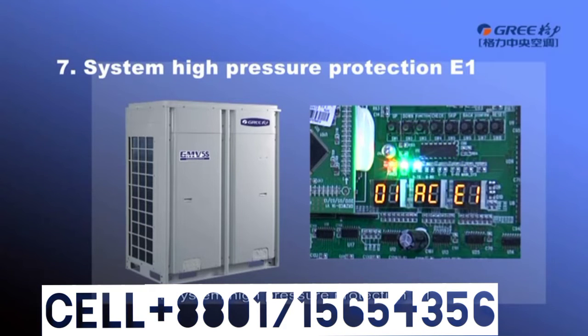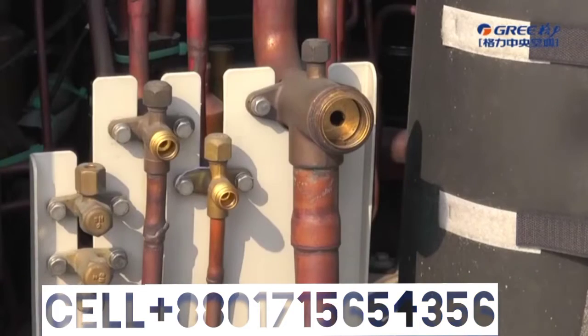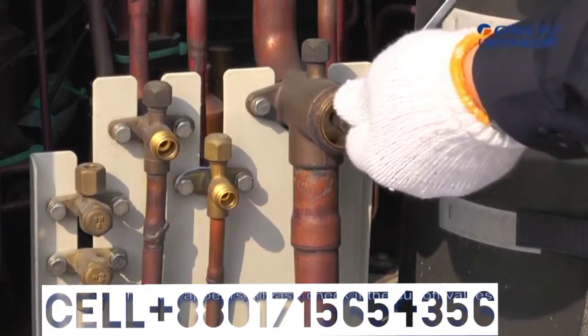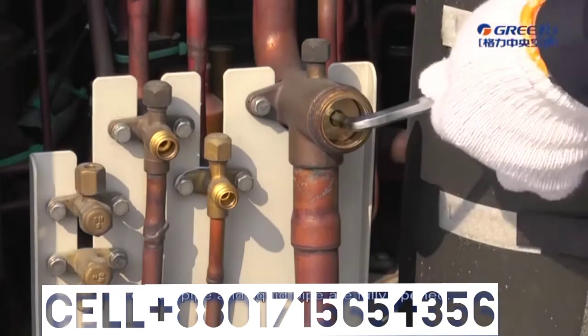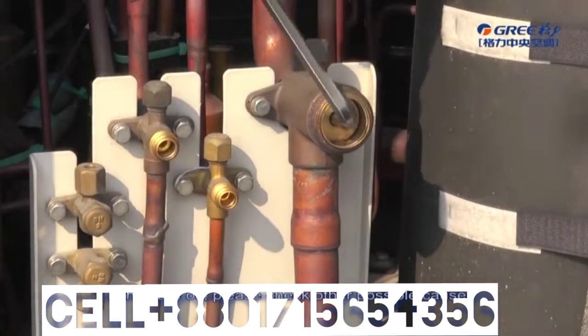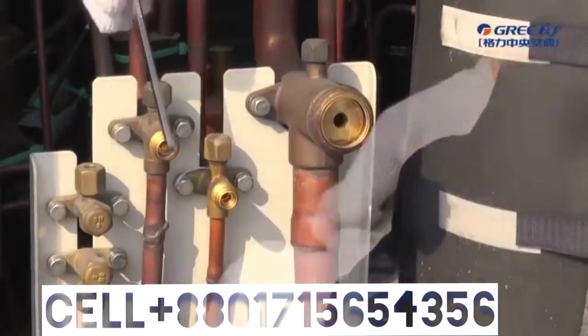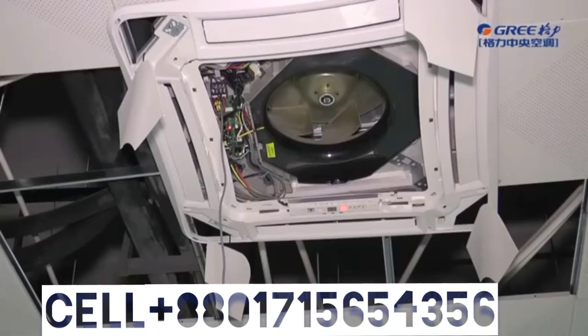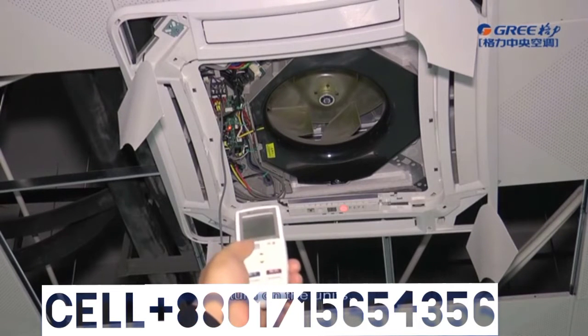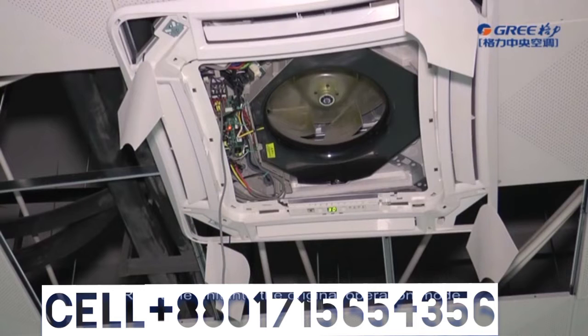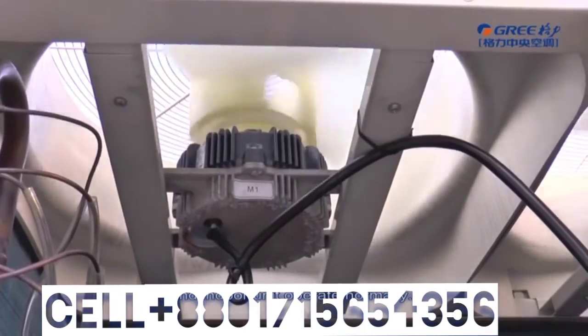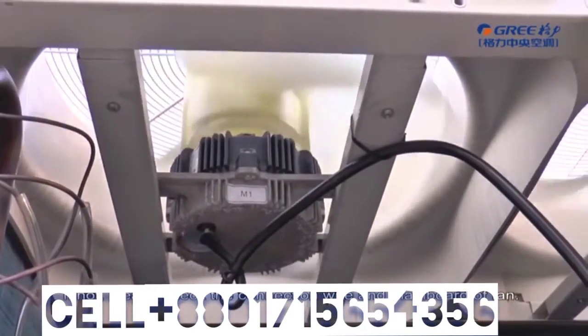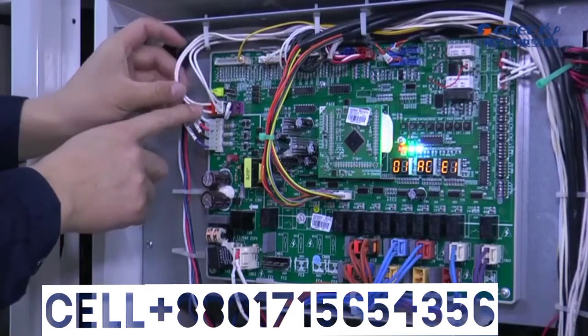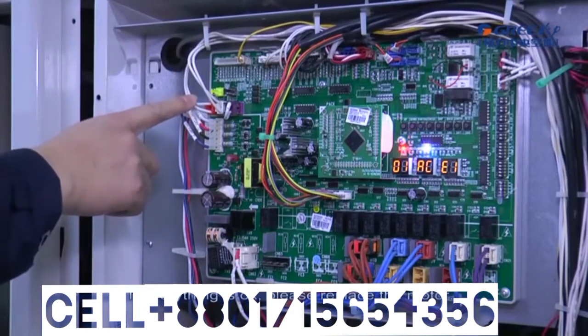7. System high pressure protection E1. When E1 appears, please check if the cut valves of the gas pipe and liquid pipe are fully opened. If they are okay, please check other possible causes. 2. When E1 appears, power off and then power on. Turn on the units. Reset the unit into the original operation mode and operation quantity, and check if the fans of the outdoor unit and indoor unit operate normally. If not, please check the connection wire and mainboard of the fan. If everything is okay, please replace the motor.